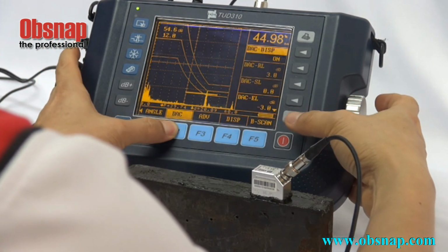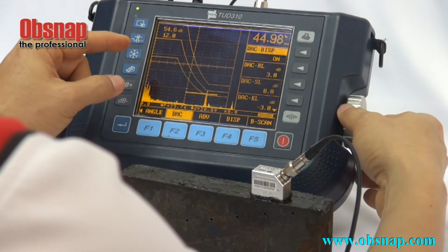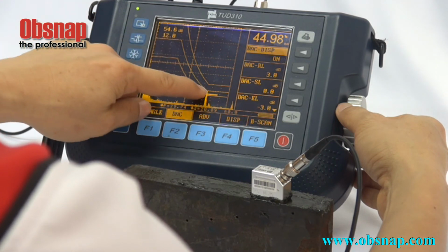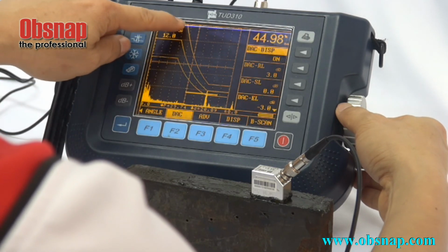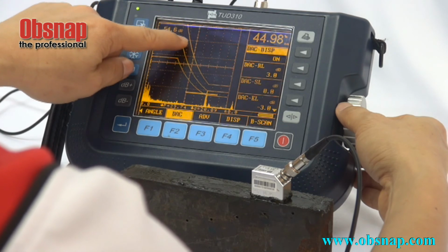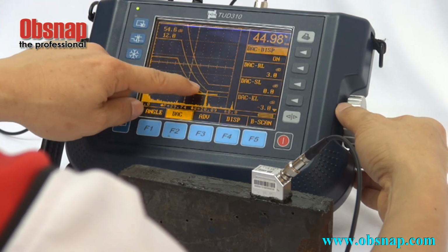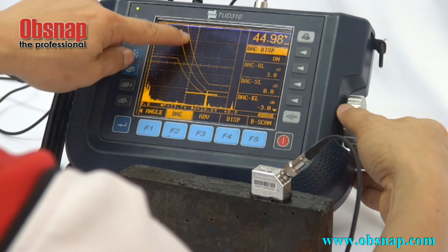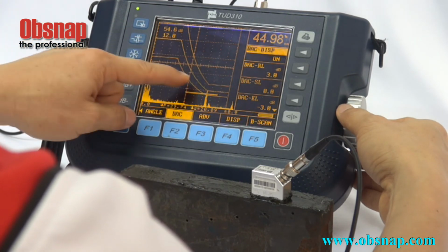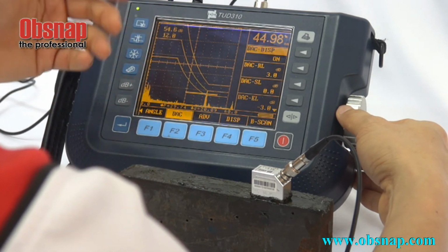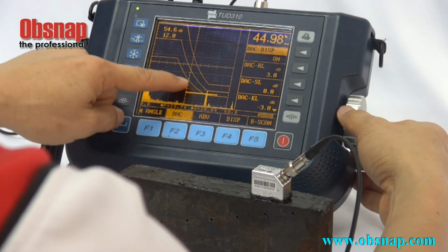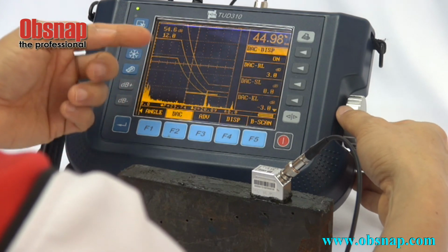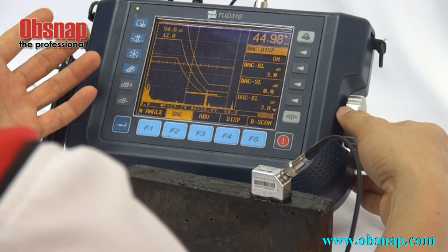Now we will be able to view or adjust this. This is actually our reference curve, and this is for the hole size of the flaw that is actually larger than 1 mm, right? And this will actually work as a tolerance band. Whatever exceeds this band, we will consider it a reject. And for whatever is lower than this reference point by 3 dB, we will say that, okay, the flaw is small enough, we can accept.